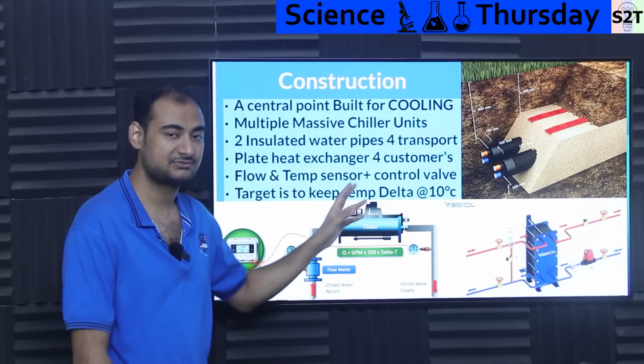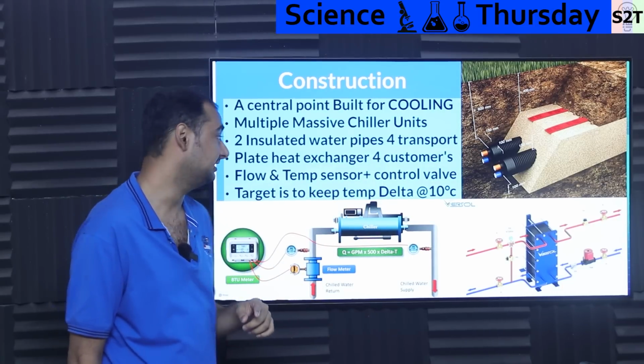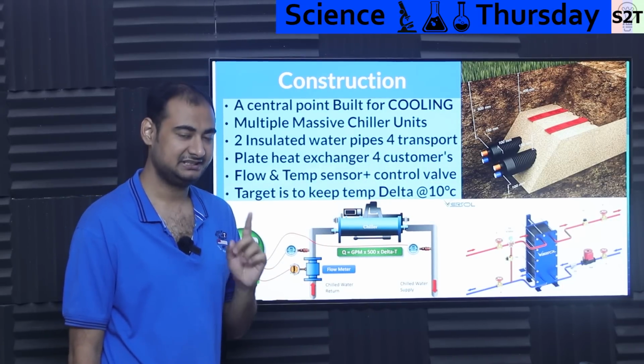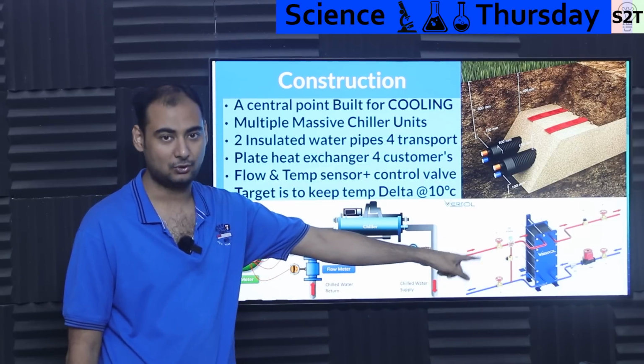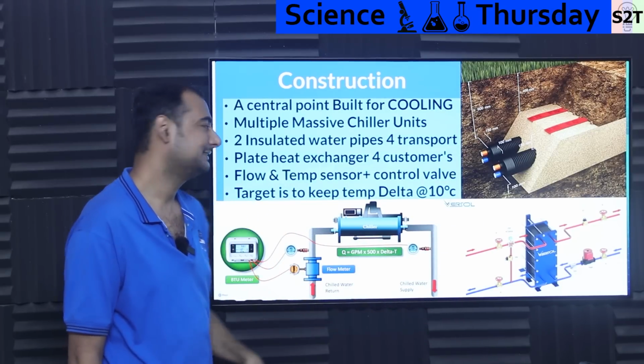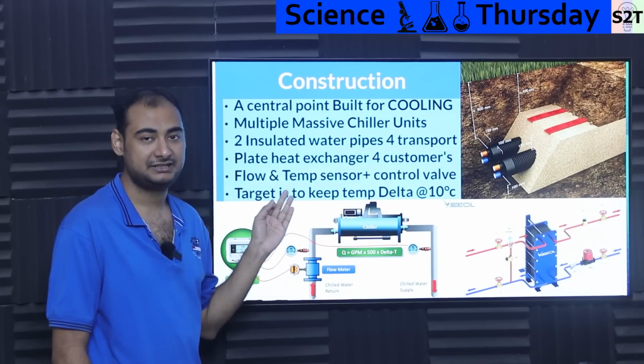Let that be very clear: most systems are designed for a 10 degree or 9 degree T delta, and that has to be maintained. Basically, they will penalize you if your building's heat exchanger isn't giving that. So that's what you do, and then you have a plate heat exchanger at the customer end.